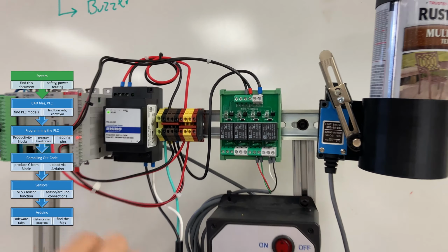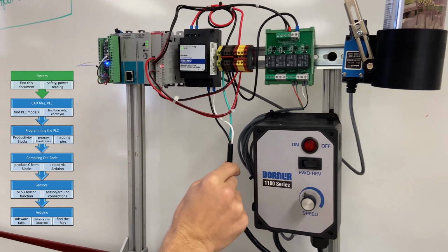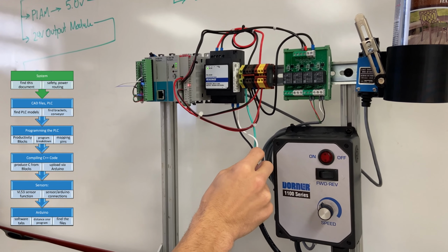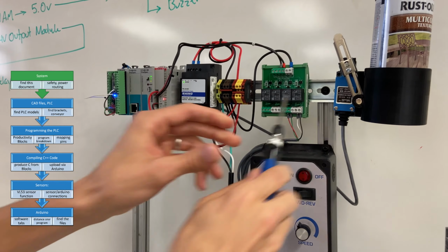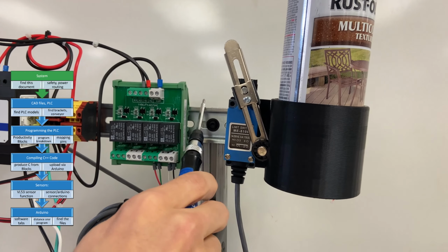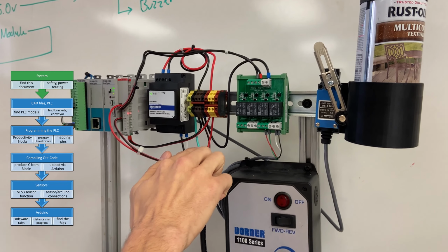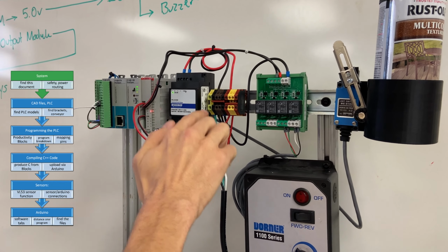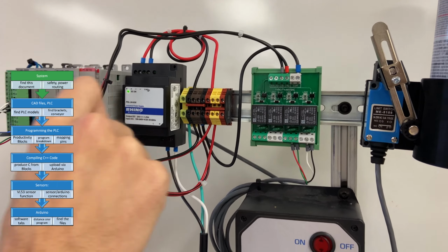And let me back up a second. When you come from here, we are immediately grounding everything coming in to this actual steel frame. So the green wire is the ground wire, and it goes into this terminal block that's blended green and yellow, and that block is actually grounded to the DIN rail itself.